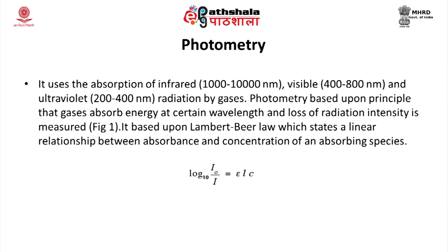Photometry uses the absorption of infrared radiation (1000–10,000 nm range), visible radiation (400–800 nm), and ultraviolet radiation (200–400 nm) by gases. Photometry is based on the principle that gases absorb energy at certain wavelengths and the loss of radiation intensity is measured. It is based upon the Beer-Lambert law, which states a linear relationship between the absorbance and the concentration of the absorbing species.